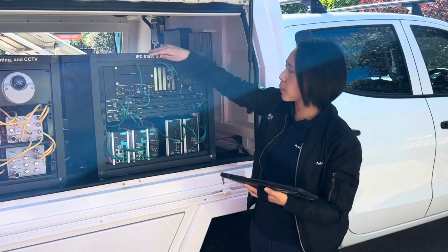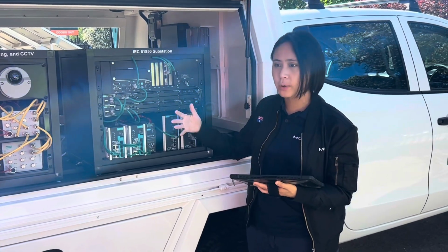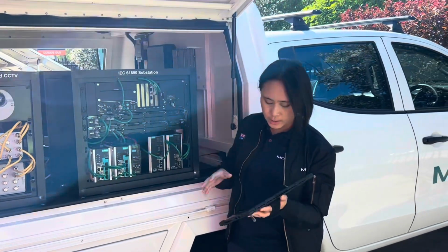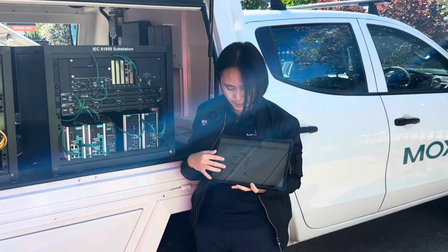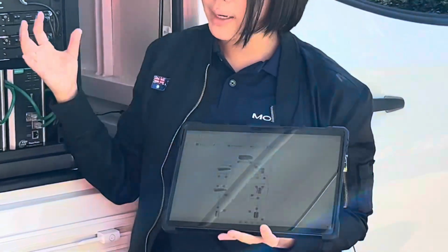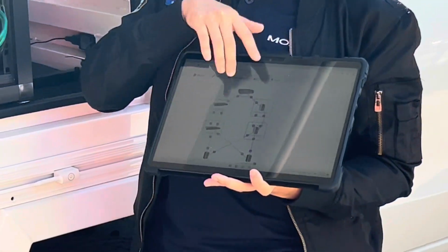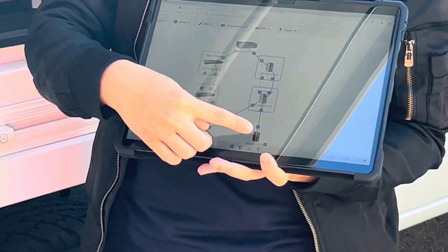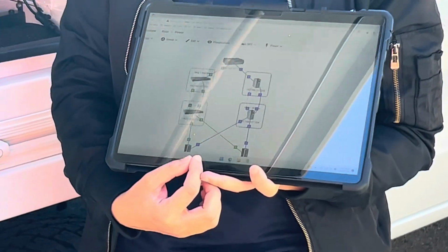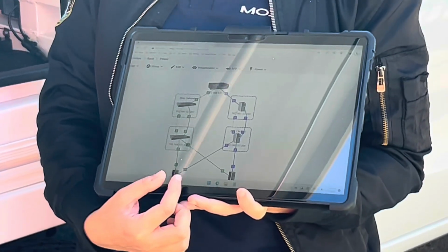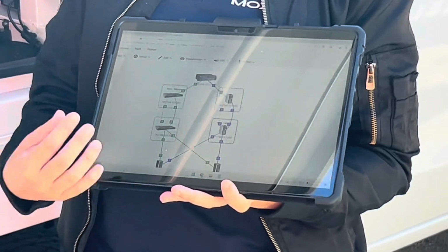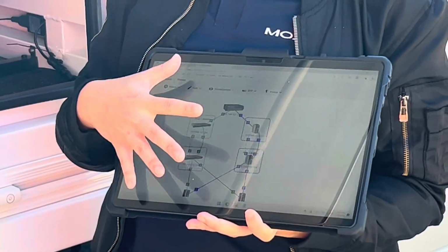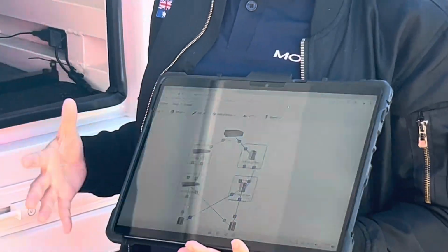So in this IEC 61850, they defined a new protocol. It's called PRP-HSR, specifically for this kind of digital substation. So their design will be looking like this. They will try to make everything in 2 copies. So from the start they send 2 copies, 1 to blue, 1 to green, and at the end point they will receive 2 copies. So if one of the copies is off, they still have the other one. So that's also the technology or protocol that we at Moxa can offer to the market.